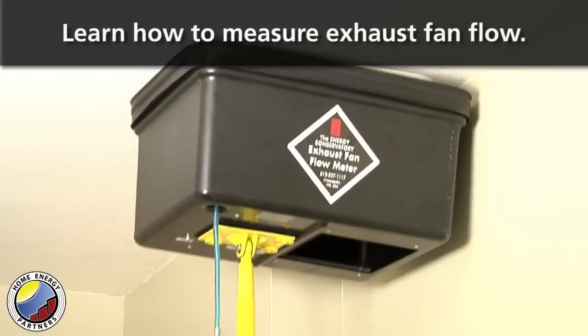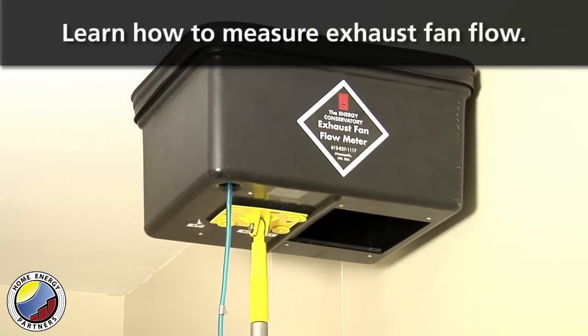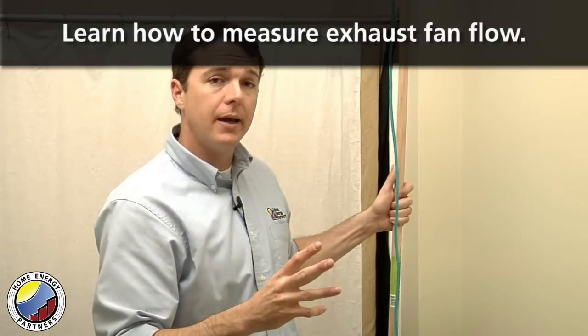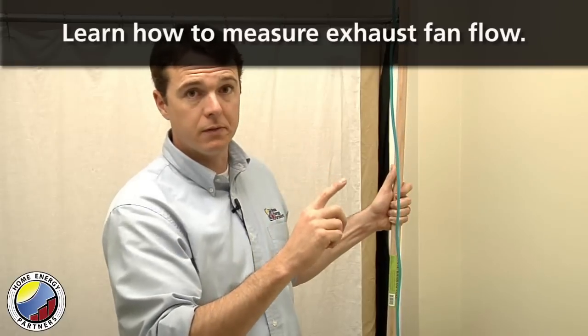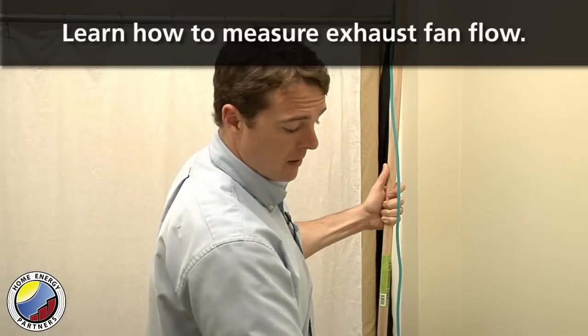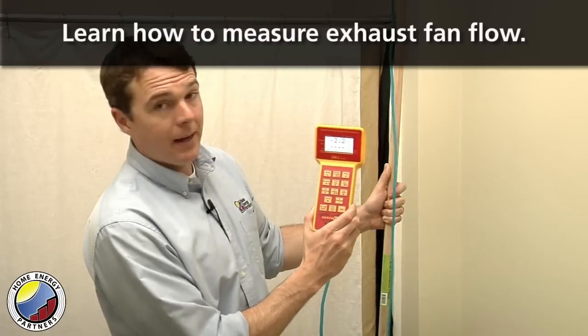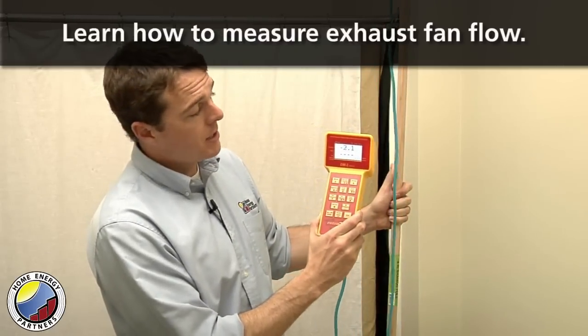At this point, all of the air that the fan is exhausting out of this bathroom is moving through the opening in the flow hood, so I can look at my gauge here and see that the pressure drop across that opening is 2.0 pascals.